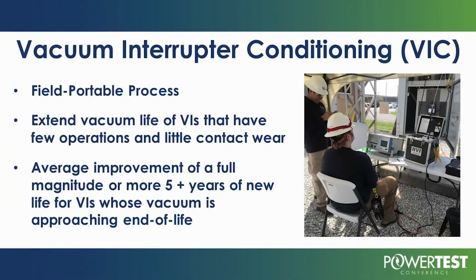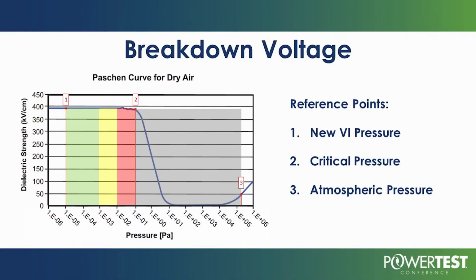What we're talking about is improving the inside pressure of the interrupter by at least 1 order of magnitude, and being able to do that multiple times over, say, a 20-year period. So if you have a mid-level interrupter that may be in the 3 PA range, which is in the middle of that chart we showed you a while ago, let's try to keep it in the 3 PA range by conditioning it every year, every 2 years, every 5 years, whatever your normal maintenance cycle is.